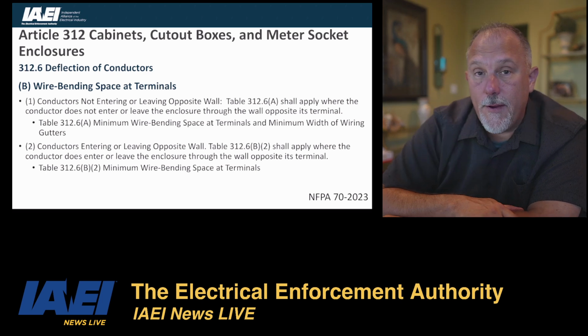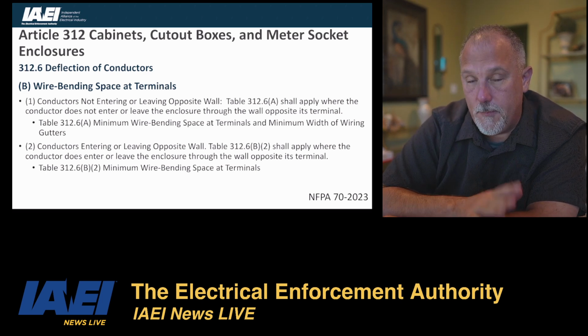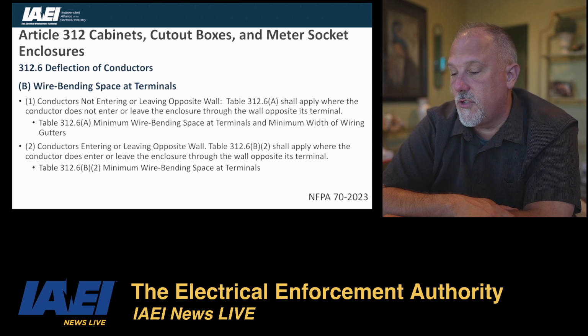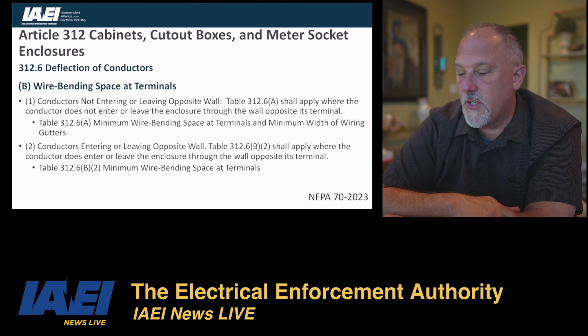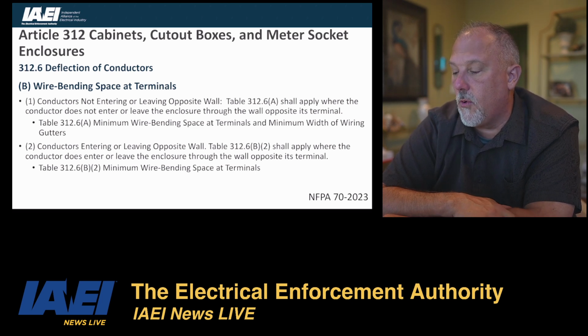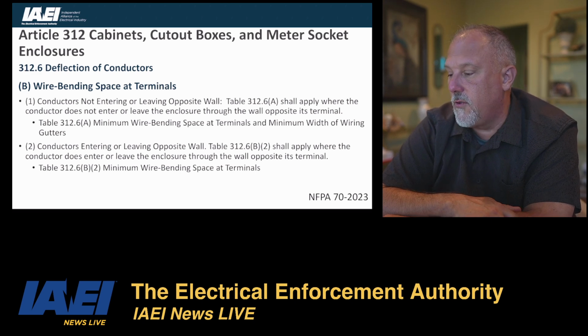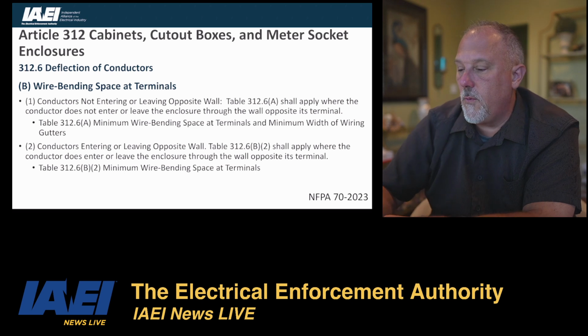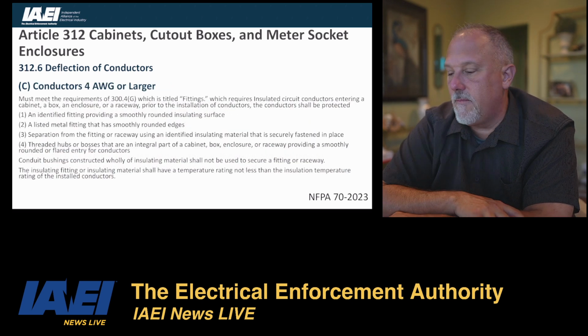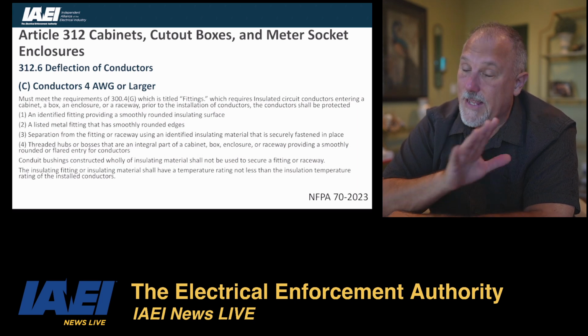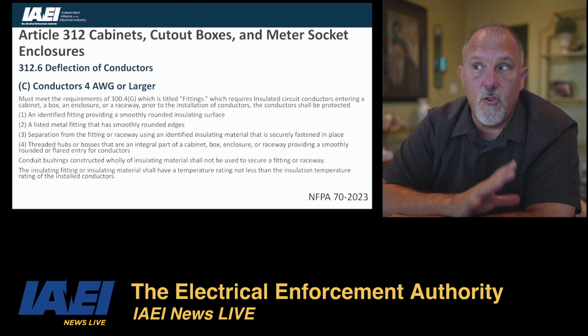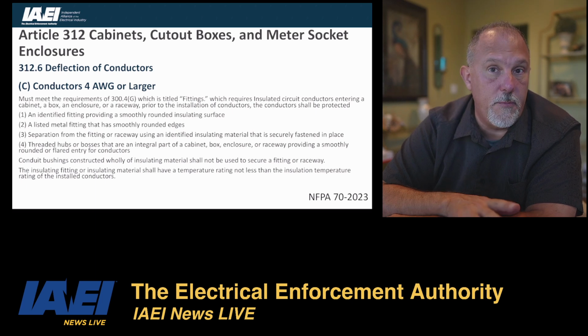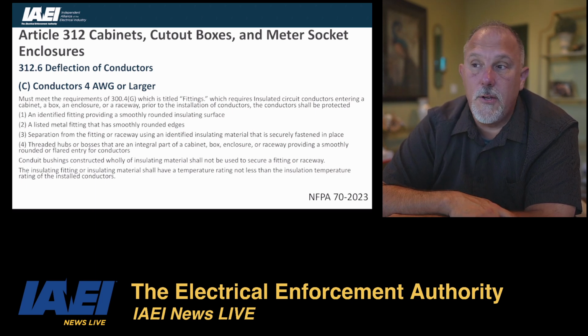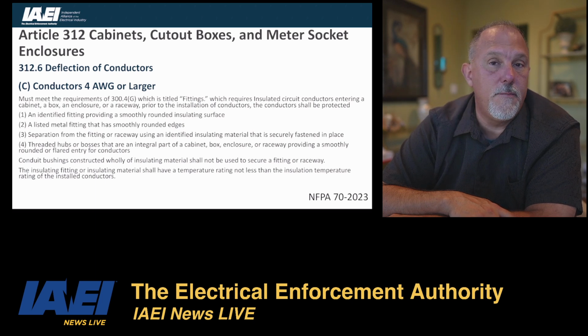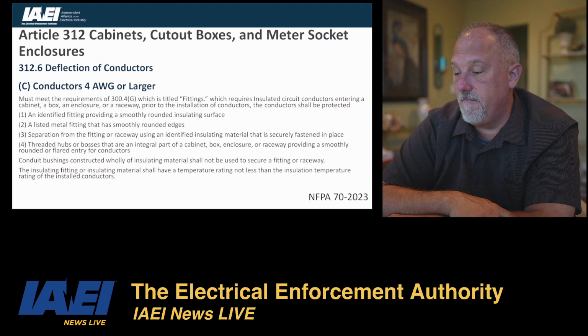You have to have good wiring. You have to adhere to the wire bending space rules at your terminals. You have conductors not entering and leaving an opposite wall, and then you have conductors entering or leaving an opposite wall. So follow all of those rules for when you're installing your conductors through that meter enclosure, which again may not just be a single meter in an enclosure. It could be multiple meters in a single enclosure. You may have a meter breaker, meter panel board, all that good stuff.